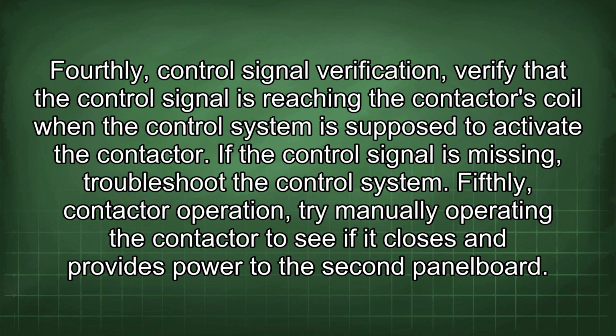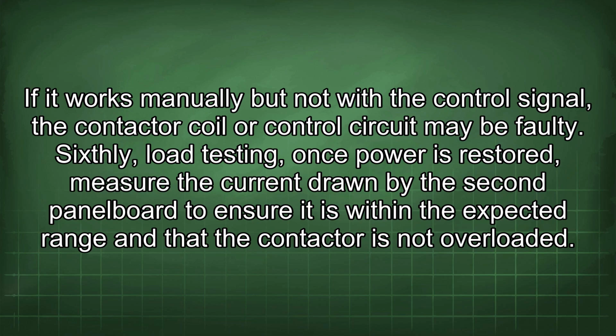Fifthly, contactor operation. Try manually operating the contactor to see if it closes and provides power to the second panel board. If it works manually but not with the control signal, the contactor coil or control circuit may be faulty. Sixthly, load testing. Once power is restored, measure the current drawn by the second panel board to ensure it is within the expected range and that the contactor is not overloaded.